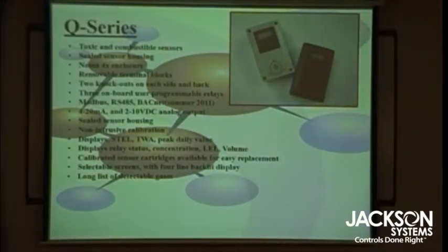We also sell the sensor cartridges, which is basically a replacement sensor with the board. So if you don't want to recalibrate it, you can buy the sensor itself and plug it in and recalibrate it. Or you can just pay $25 to $40 more and have the sensor already pre-calibrated, and you just go in and plug it in. So it depends how many sensors you have and what's most economical for you.